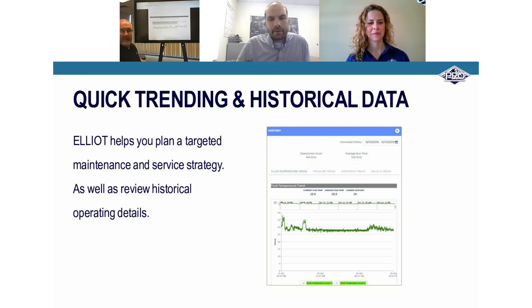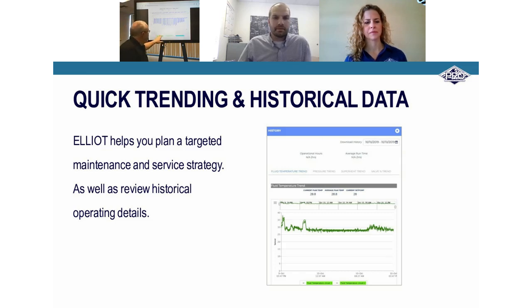I'm going to show you, if you got a sec, I'm going to jump over to the refrigerant pressures, because that's a graph that when you're looking at it visually, it's kind of a lot of noise going on right there. So if I want to dial in, just like John mentioned, specifically to circuit 1, I can shut off by selecting down on the bottom row. I can shut off the suction pressure or even the discharge pressure and look at those trends and see, okay, what was happening in my run cycles. And then if I want to dial in, maybe it's not a suction pressure issue. Maybe I'm thinking discharge pressure could be the issue. I can close that out, look just at discharge pressure, and really zoom in and get down to a specific time frame.